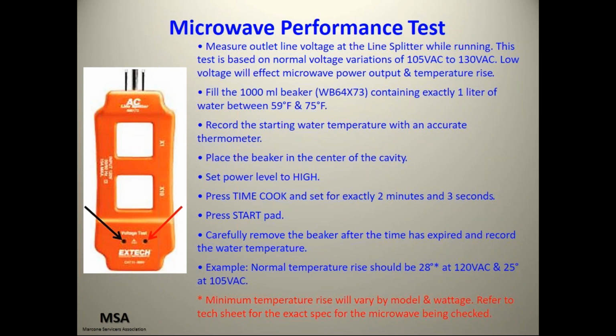And they have it down here in red, so I can barely read it, but it says minimum temperature rise will vary by model and wattage. Refer to the tech sheet for the exact spec for the microwave being checked. So what you're doing is looking at the temperature rise of that 1,000 milliliters of water in that microwave for 2 minutes.